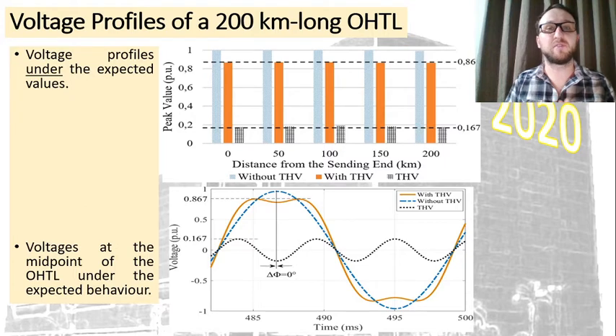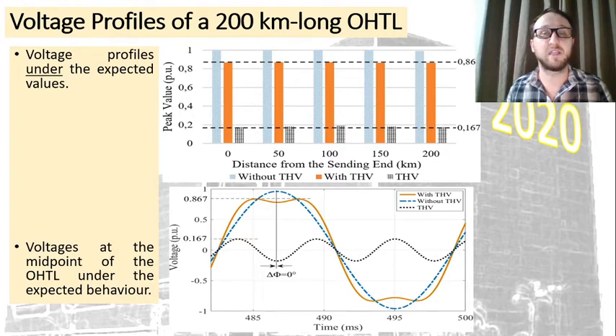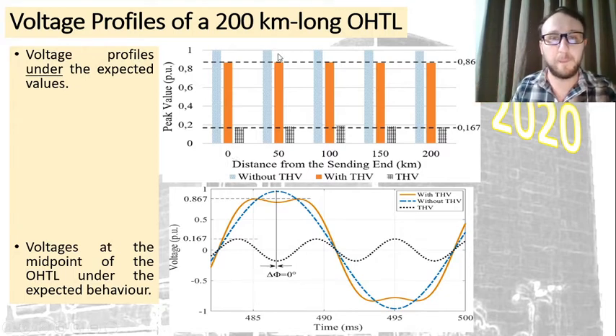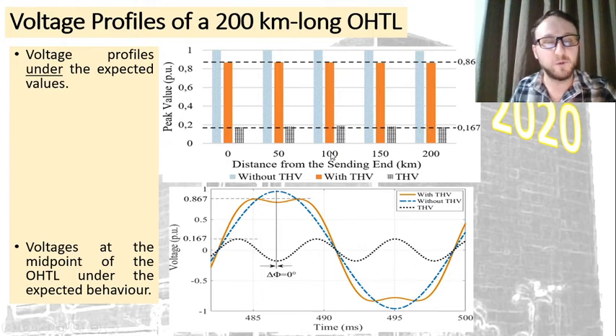So we start from 200 km up to 600 kilometers for a 230 kilovolt line. For the first line studied, 200 kilometers, we divided the line into 50 kilometer sections, and we apply the voltage with the fundamental one and with the THV, and we also measured just the amplitude of the THV component. The resultant voltage at the midpoint of this line is represented here, so the orange one is the one we want to focus our attention on, and it gets up to this amplitude here.